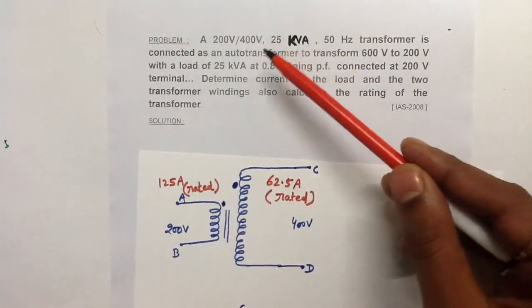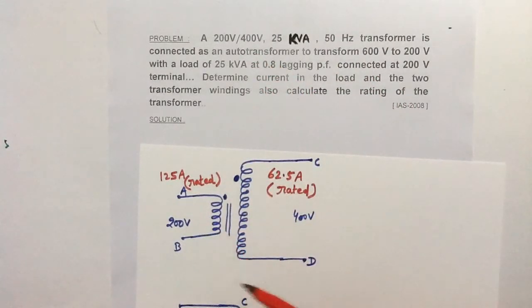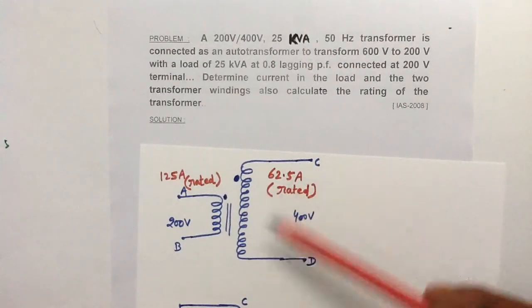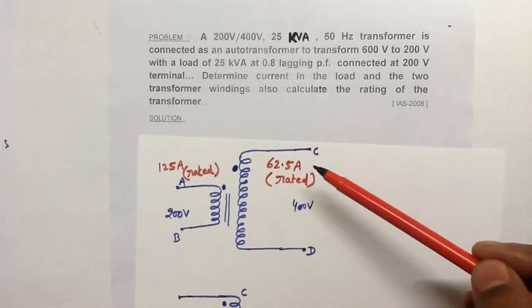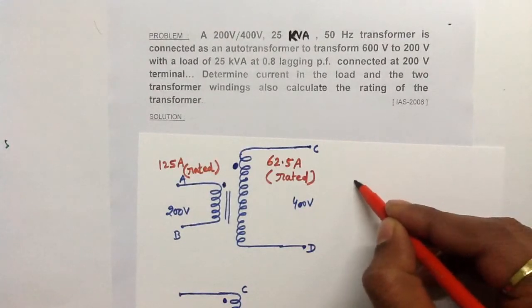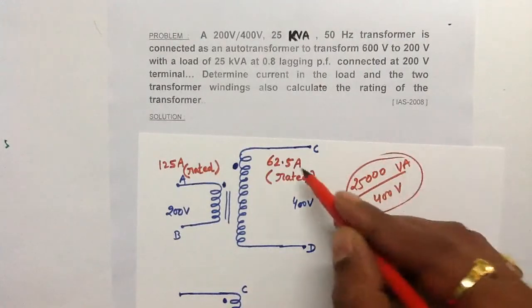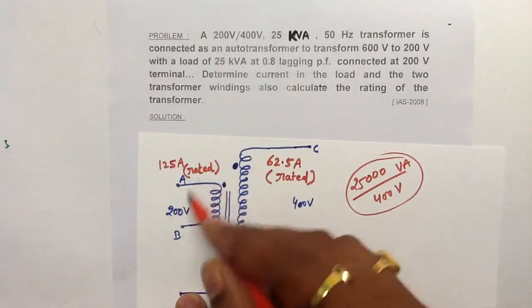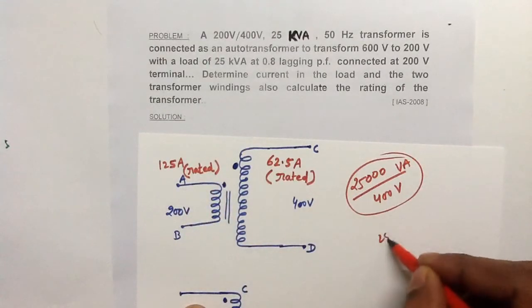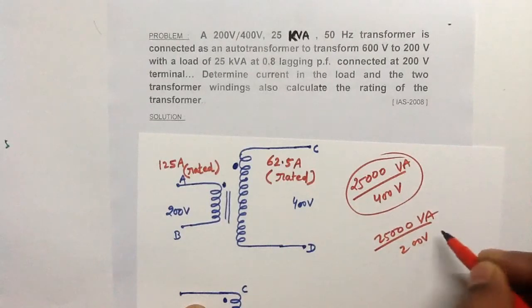The rating of the two-winding transformer is 25 kVA, 200V/400V. Using this rating, we can find the rated current in the HV winding: 25,000 VA divided by 400 V gives 62.5 amperes. The rated current in the LV winding is 25,000 VA divided by 200 V, which gives 125 amperes.